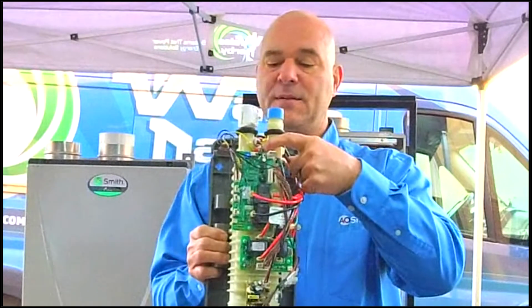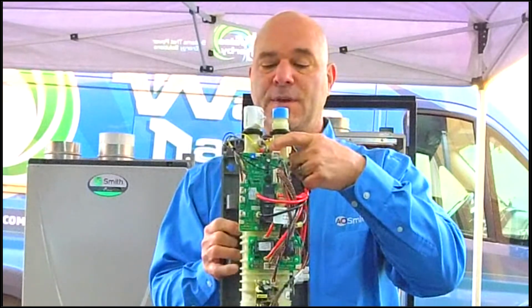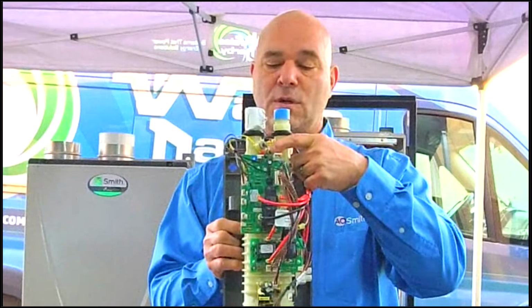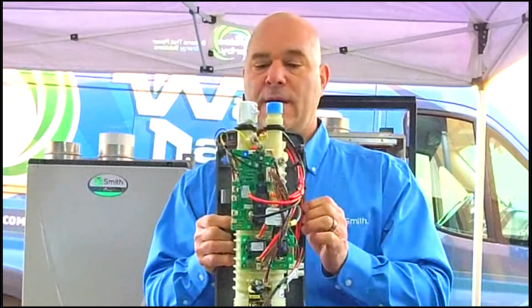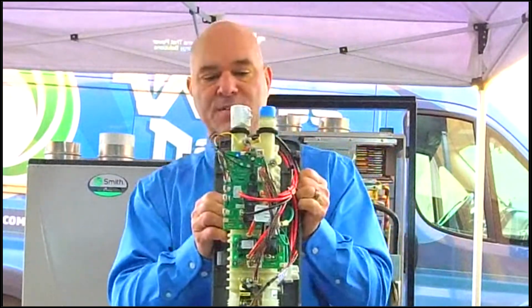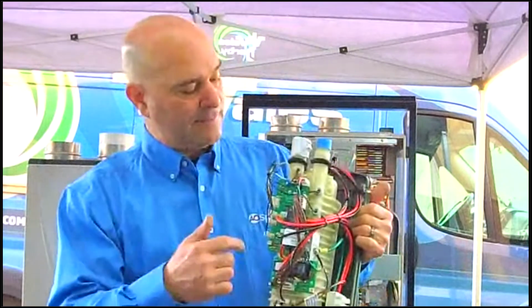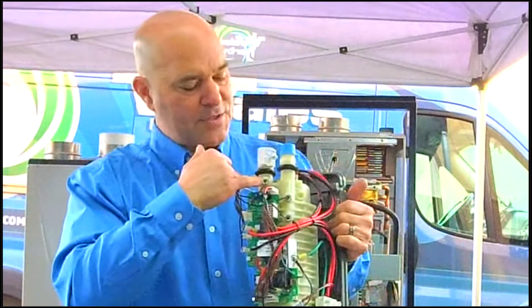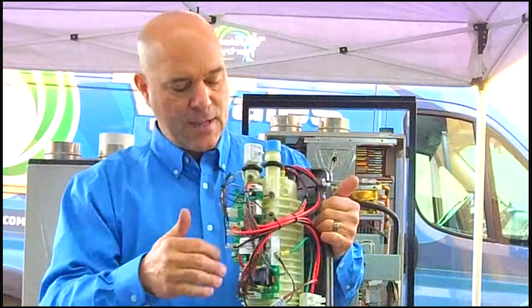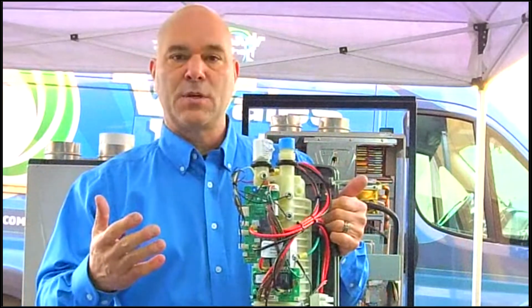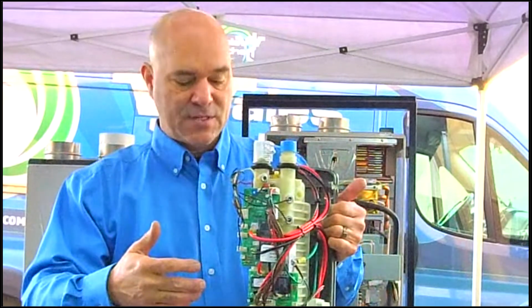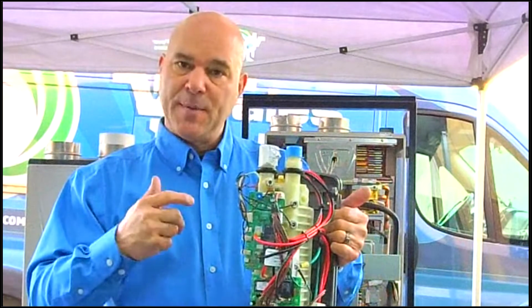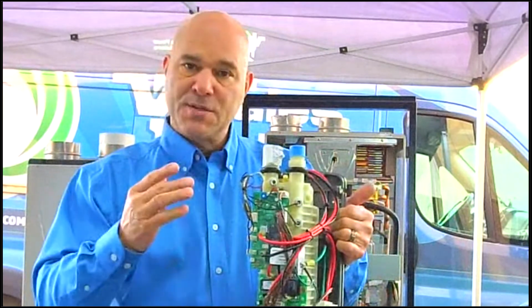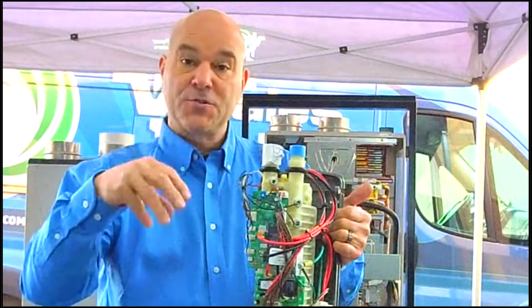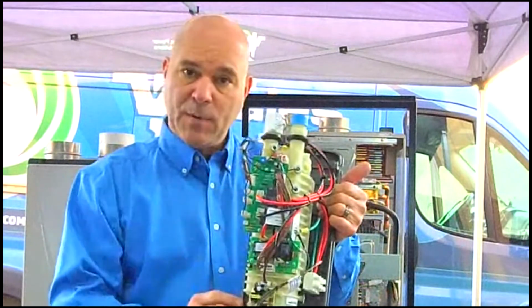We protect the element with a little grounding screw here that will tell us if there's water in the element itself, around the element, I should say. And in addition to that, we're taking our temperatures here with thermistors. That's what tells us when there's a water demand, when the house is looking for water. The other thing we're able to do here, it's built into the boards, we're able to trickle charge the water to keep it warm.